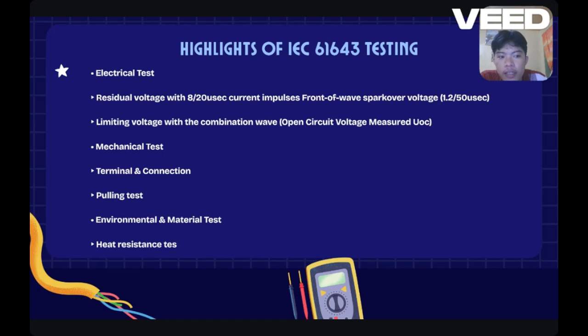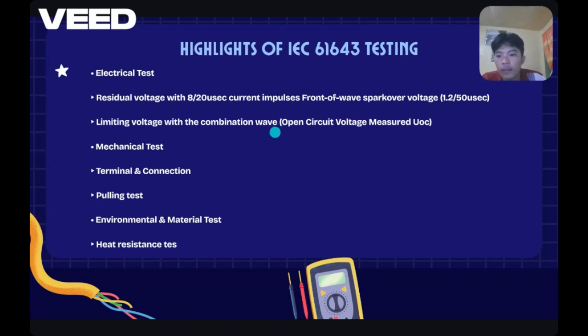So we have highlights of IEC 61643. First is electrical test: residual voltage with 8 over 20 microsecond current impulse, front of wave spark over voltage 1.2 over 50 microseconds, then limiting voltage with a combination wave open circuit voltage measured. Then mechanical test: terminal and connection, pulling test. Then environmental and material test, heat resistance test.